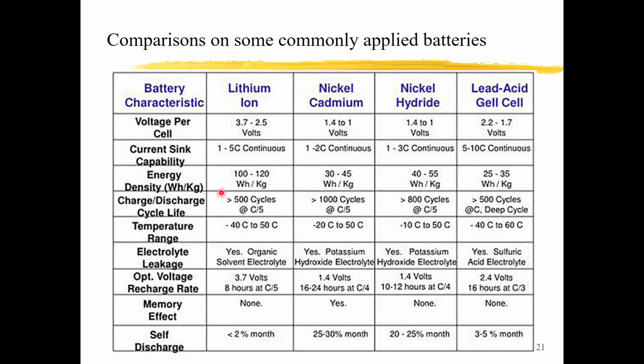Okay, and the temperature, the cycle life. The cycle life, basically the lithium ion batteries have medium cycle life, and the nickel cadmium has the highest cycle life here. And lead acid can be used only for a few cycles. The cycle life is very limited, and the number here is higher than 500 cycles. I have to say, this is lead acid gel cell. There are different kinds of lead acid battery, and for other kinds of lead acid battery, the cycle life is even shorter.